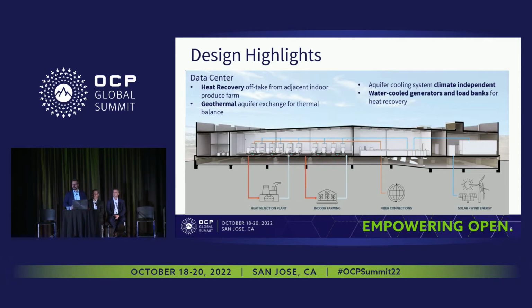So those generators are water jacketed. The load banks required for commissioning, annual testing, and monthly maintenance are water cooled. All of that heat that we typically would reject to the ambient is recovered and put back into the heat exchange. We're able to reuse even some of that preventative maintenance excess in our heat exchange.